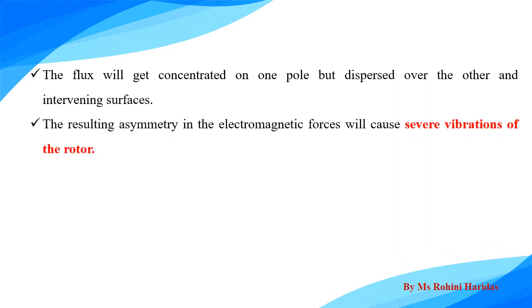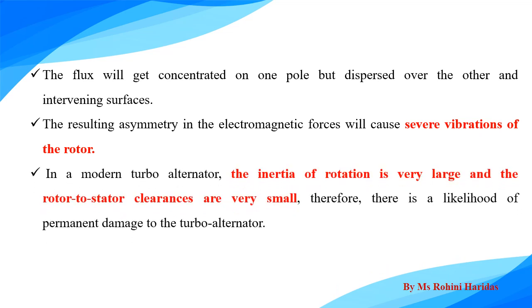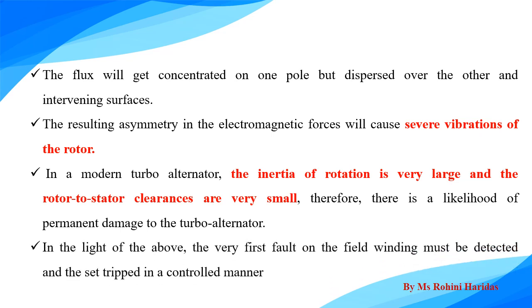The flux will get concentrated on one pole but disperse over the other and intervening surfaces. The resulting asymmetry in the electromagnetic forces will cause severe vibrations of the rotor. In modern turbo alternator, the inertia of rotation is very large and the rotor to stator clearances is very small. Therefore, there is a likelihood of permanent damage to the turbo alternator.